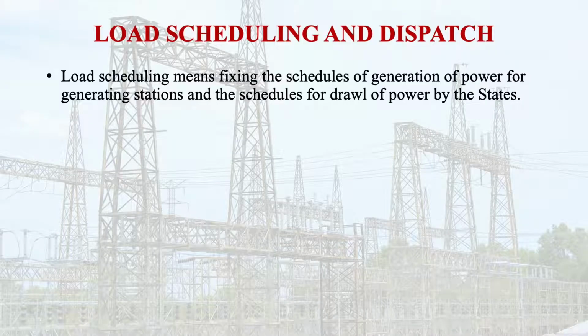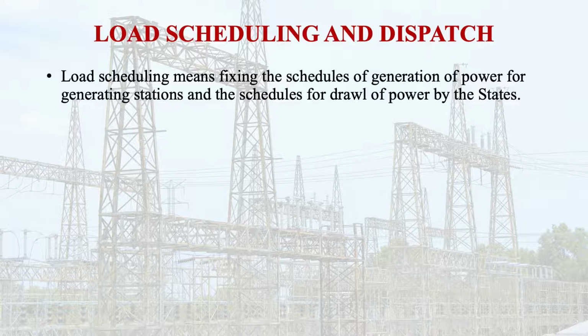Load scheduling means fixing the schedules of generation of power for generating stations. Generating stations are producing the power, so it is necessary to fix the schedule for their generation and the schedules for the draw of power by the states, because the power is drawn by the states as per their load requirement, so their schedule also needs to be fixed. So load scheduling means both sides. That means the scheduling of the generation side and the scheduling of the draw of power by the states.